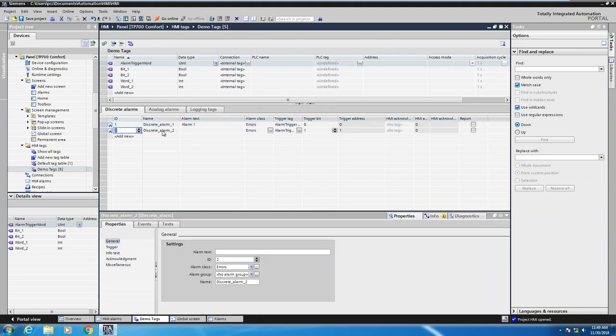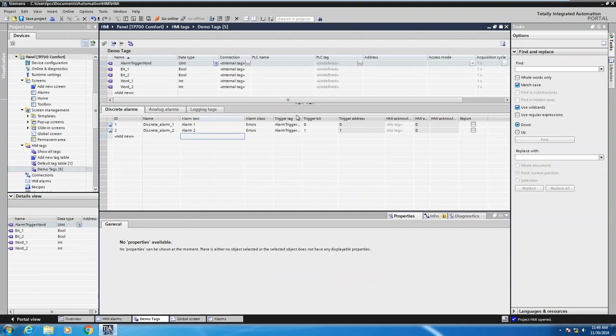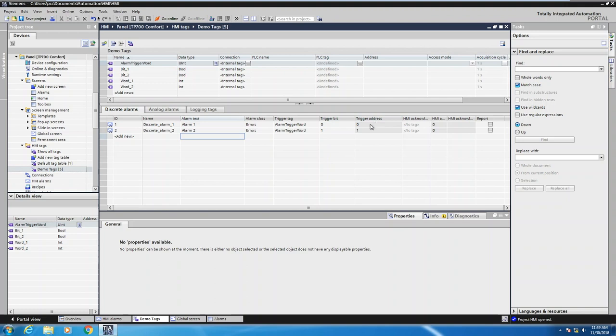I'll click Add New again and add my second alarm — this one is called Alarm 2. Now if you look at the alarm trigger tag, it is also selected but the bit number has incremented. One important thing to point out: the trigger address column is a read-only column. This column will be filled in with the actual PLC address of the bit that needs to be triggered for this alarm, since we are picking bits out of a word. That is a very important column to remember.